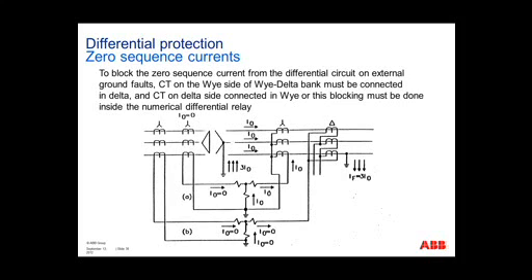So to block zero sequence current from the differential circuit, we can do this by utilizing the Delta connected CT on the Y side of the transformer. In this example, let's concentrate on the CTs closest to the transformer. The CTs are both connected into Y. We can see that the Delta side of this transformer has no source of zero sequence currents, so the relay will not see zero sequence currents.